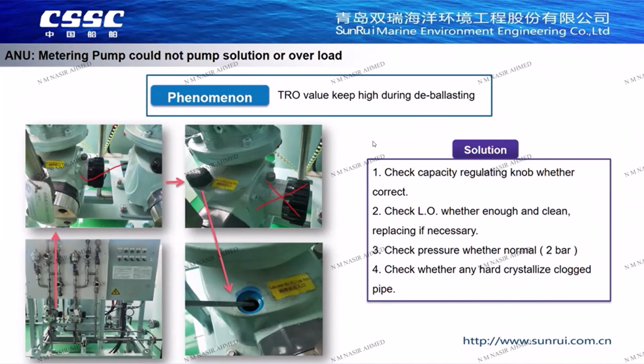The second metering pump cannot pump neutralizer, or the pump overloads. It can be observed that the TRO value during deballasting is always high and the ANU liquid level cannot decrease. It is necessary to check whether the adjusting knob of the metering pump is in the correct position. In normal operation, the knob should be rotated to the bottom, about 90% of the displacement. Turning the knob outward will reduce the displacement of the pump.